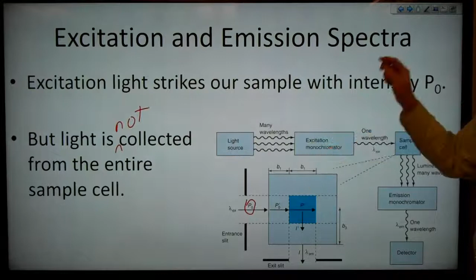The excitation light is striking our sample with intensity P0, so that's this amount of energy coming in, but light is not collected from the entire sample cell. Instead, light is collected only from this central region, only from that central darker portion there. So we need to be concerned with the intensity of light that makes it to that central region, which is P0 prime. Some amount of light will get absorbed between when it enters the sample and when it reaches that central region.